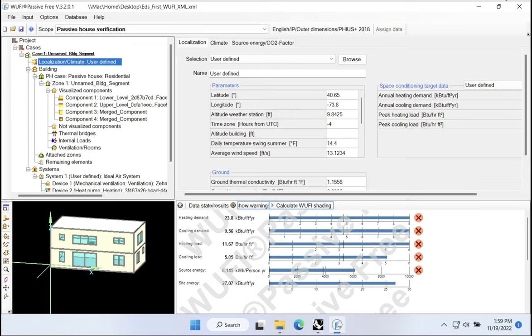One thing to keep in mind with PHIUS certification is that the targets are going to fluctuate and shift around, depending not only on your climate, but also on your building type, the size of your building, the number of dwelling units, etc. So the PHIUS targets are always moving, and we need to use the PHIUS online calculator to figure out what those threshold targets are for our building, and then enter those into our WUFI passive model. We actually don't know what the targets are until we've built out the first version of the model. We've been able to capture some relevant data around total ICFA as well as total envelope area, and both of those are going to be important inputs.